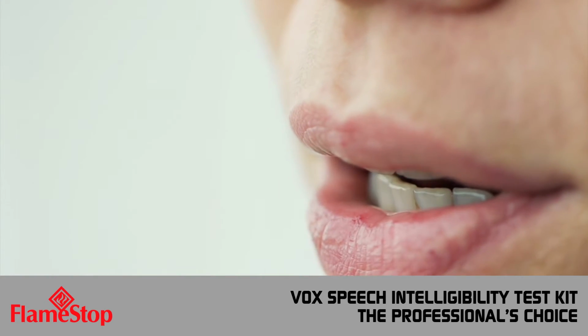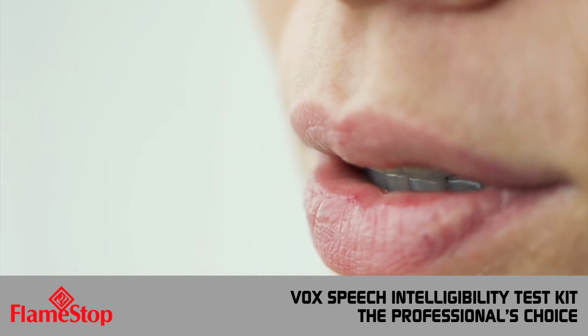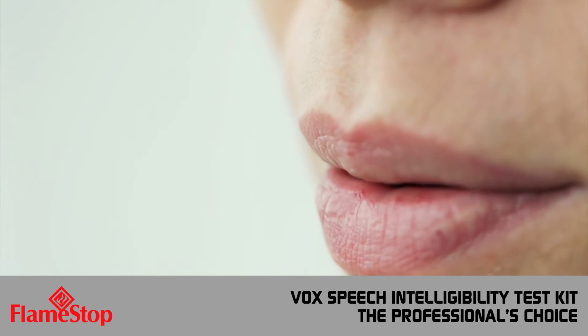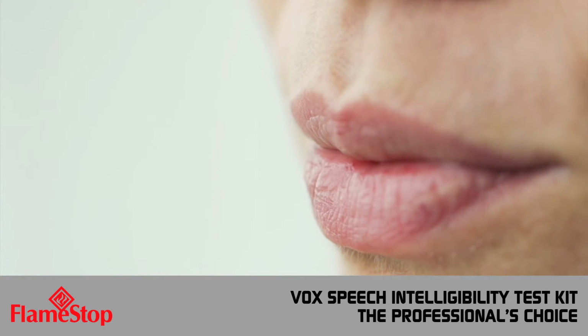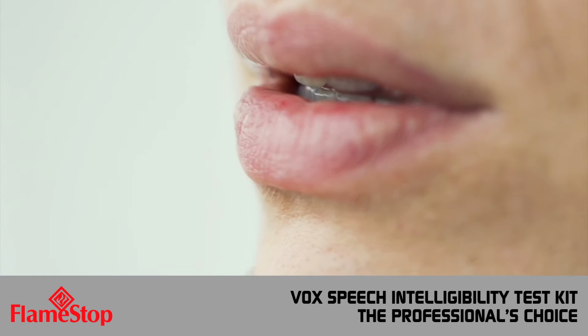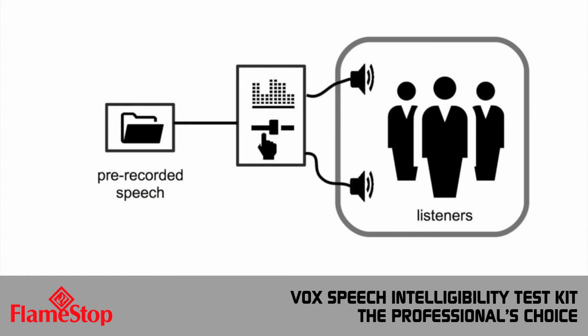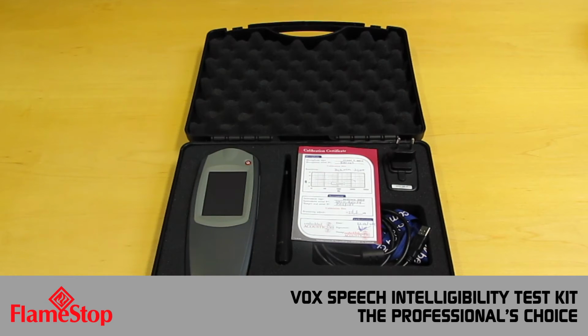Before any STIPA test, the talker is always replaced by an artificial source of the STIPA test signal. What signal source to choose depends on the kind of system you are testing. Some public address systems make use of pre-recorded messages. In those cases, simply upload the STIPA test signal as if it was a new spoken message. The STIPA test signal is provided on a flash drive bundled with every VOX.